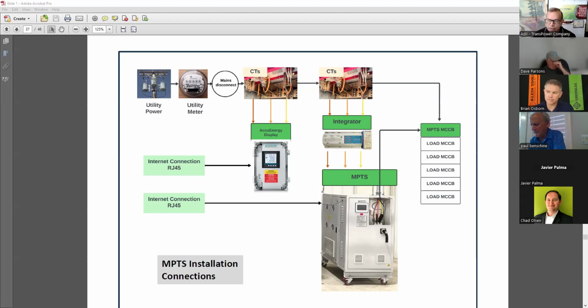According to code you need that. And according to code, if you install the MPTS beside your switchgear and it is within line of sight, you don't need another disconnect or another MCCB like it's shown here. Let's say this is your switchgear and the MPTS are in the same room - you can tap power straight from the bus bar and connect it here because it's line of sight, because you can lock this up and work right there.